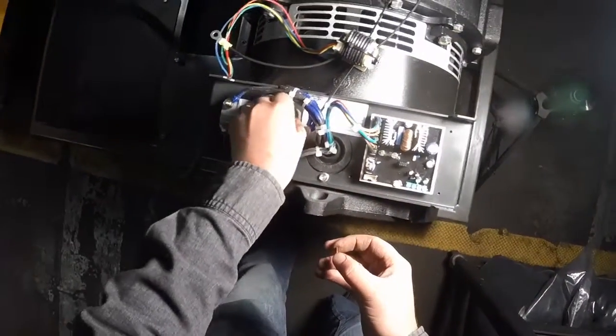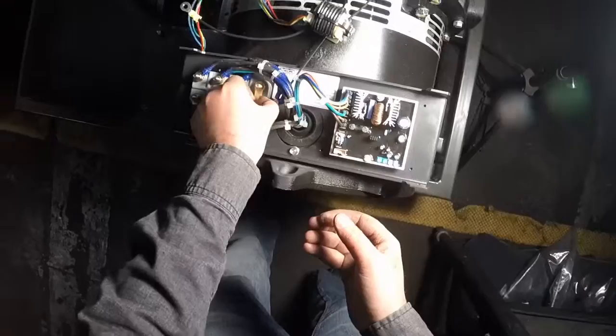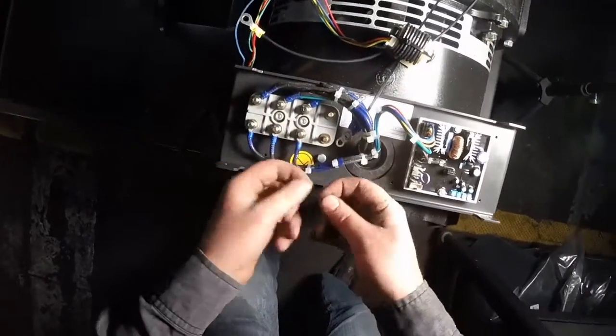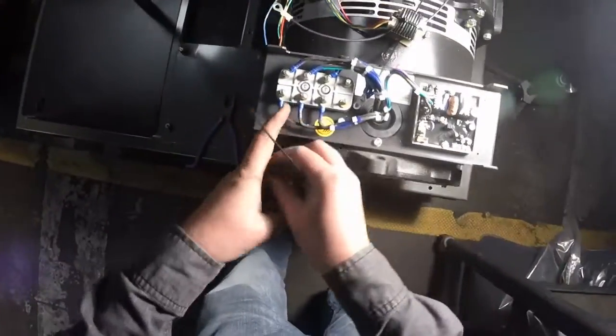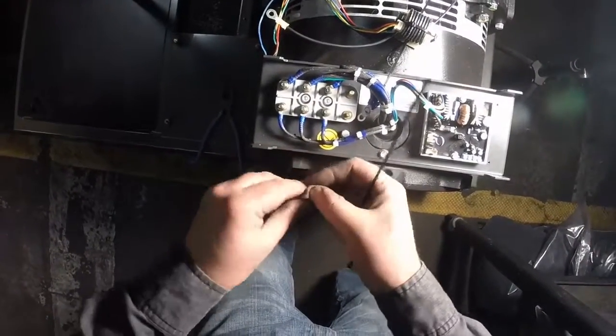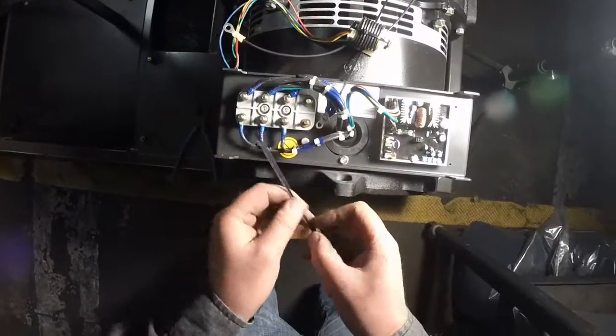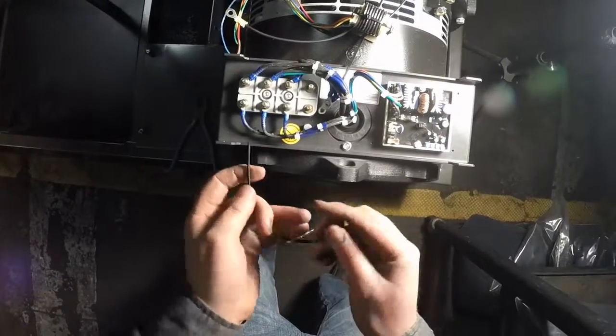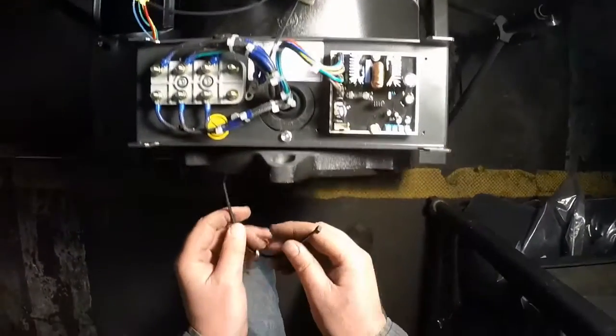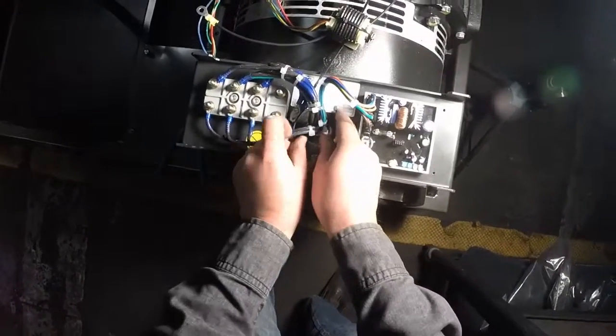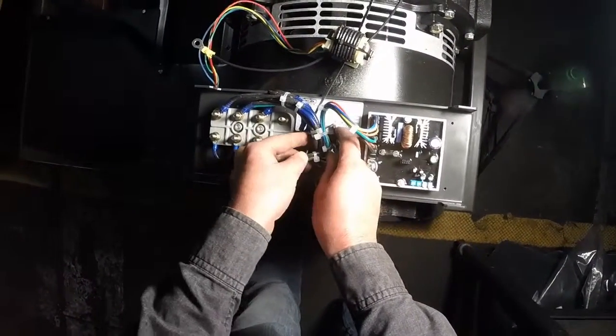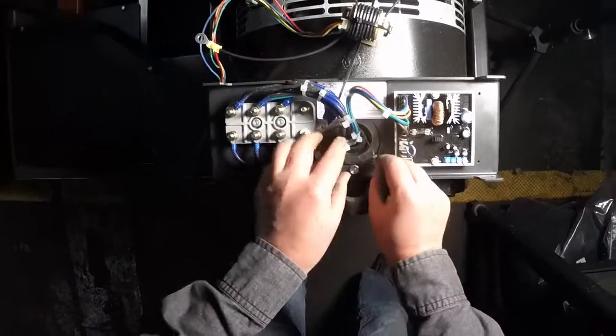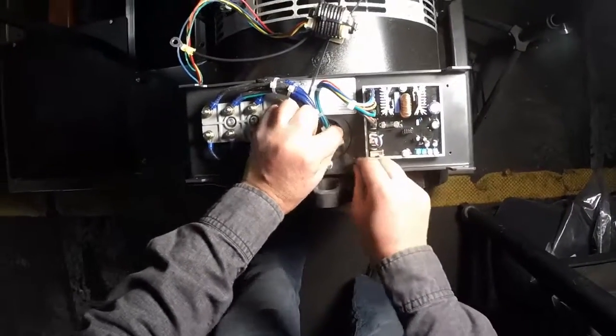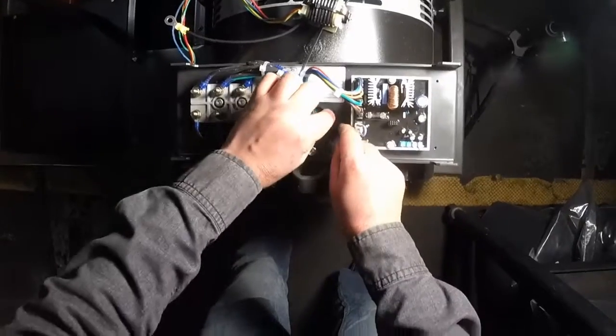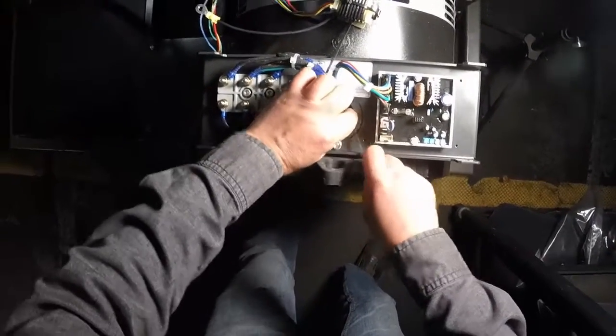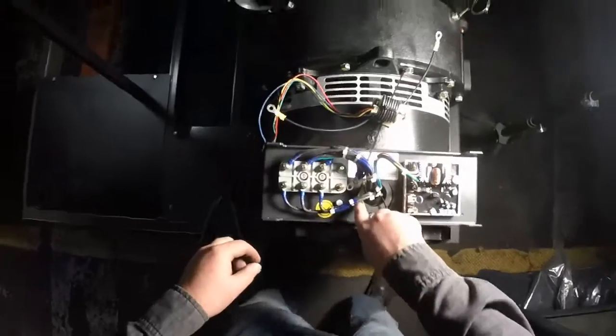And I'm going to remove all of these bus bars, these brass bus bars, from this. And I'm going to use a zip tie to tie them together and not lose them. I'd recommend tying them to the equipment itself, but in a place that is not going to end up shorting anything out, so I'm going to tie them down here. Might be best to put them in a Ziploc bag or insulate them with some tape, just to avoid that risk, but we're going to tie them down there.